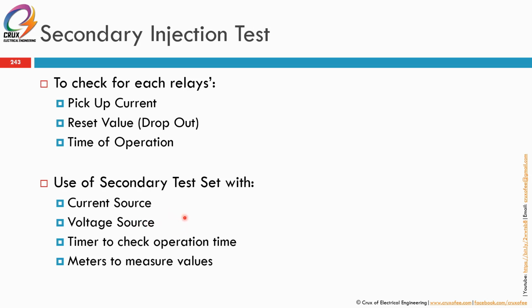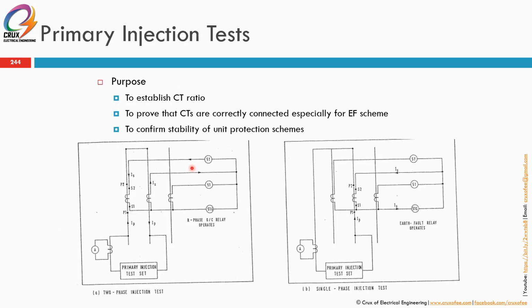Okay, you don't have to write down anything. You just do the test. 10 relays, 20 relays, 100 relays. Make sure the tagging is input correctly for every test. Then you can just print out the test results. No need to write down and transfer all the data from your hard copy back to the soft copy online. Okay, that's secondary injection test.